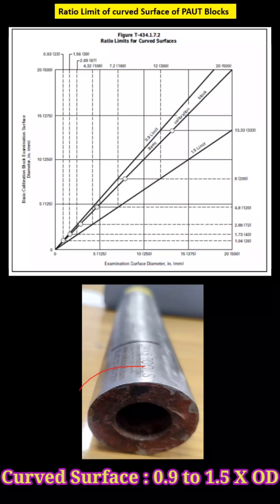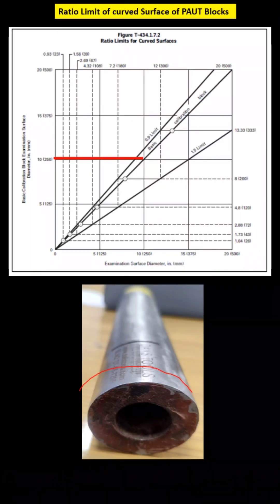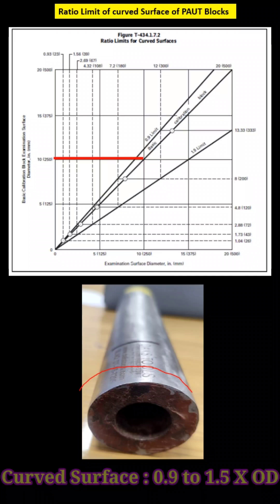For example, this is the curved surface. If you are using a 250 mm curved surface basic calibration block, we can use the job from 250 times 0.9, which is 225 mm, and the maximum limit will be 1.5 times 250, which is 375 mm.